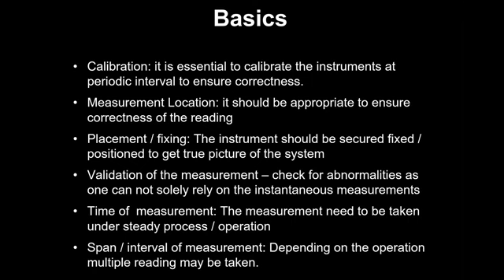So they started asking why there is a difference. Then I said, let me go and see, because I had not gone to the site. My team had gone and they were doing the measurement. When I went, what I saw was the probe was inserted, but there were some gaps. Now you would be aware that the entire ducting system is under negative pressure. If you don't seal it properly, the air from the atmosphere is going to go inside.